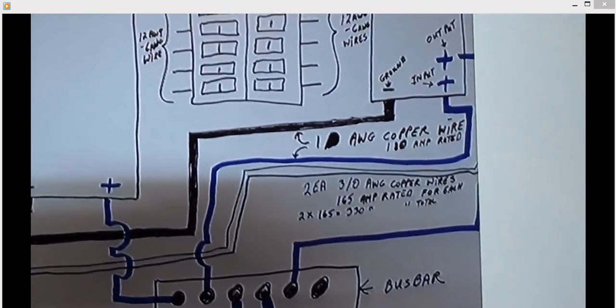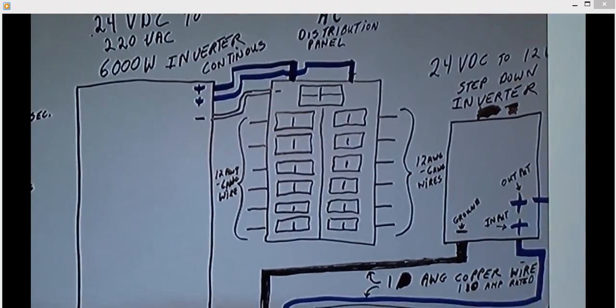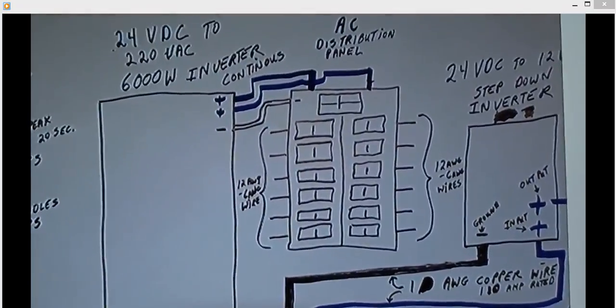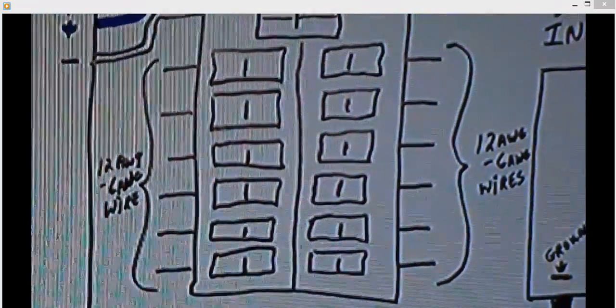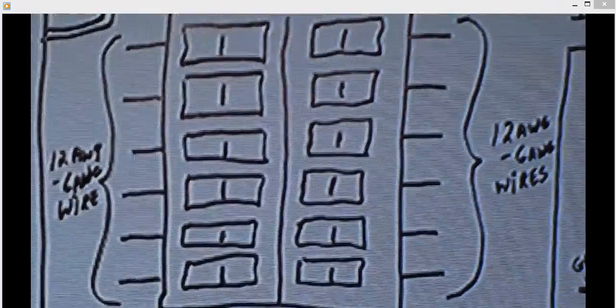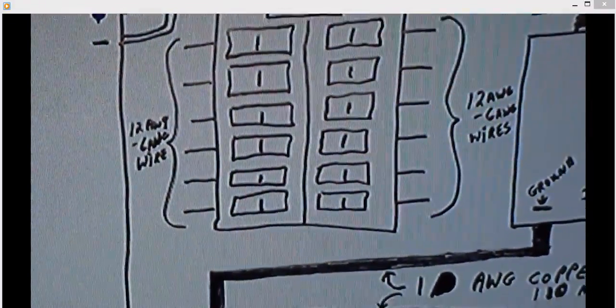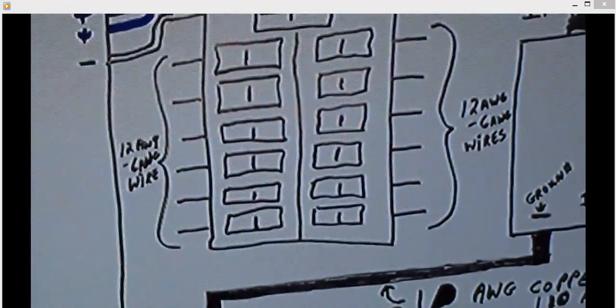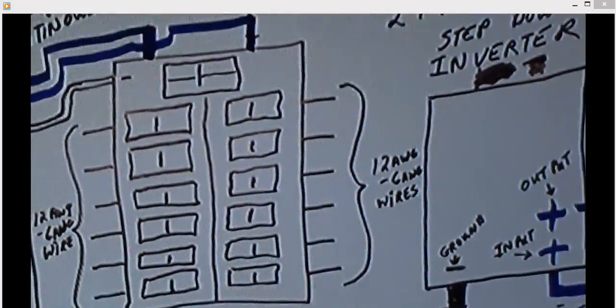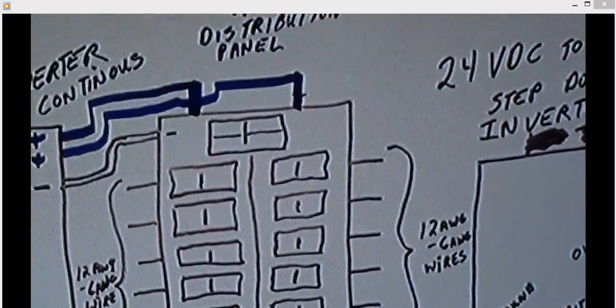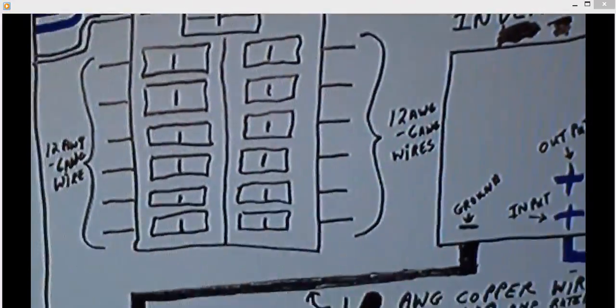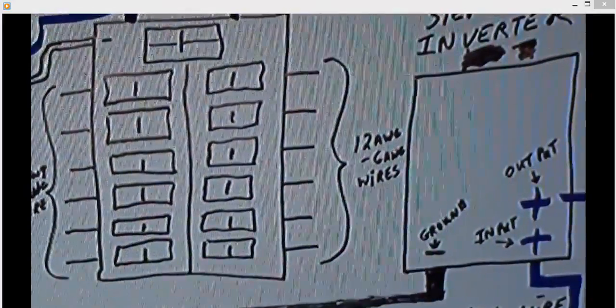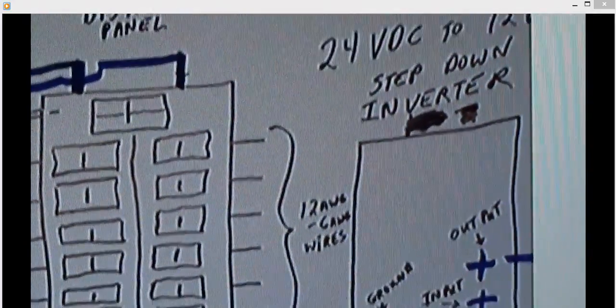Now if we look up here on the distribution panel, this is what's normally in a house. You have 12 AWG wires and 6 AWG wires coming out of your circuit breakers, depending on what they're rated at. So if you've got 6 12-gauge wires coming out, how in the world are 4 AWG wires going to handle all 6 of those? It can't be done.